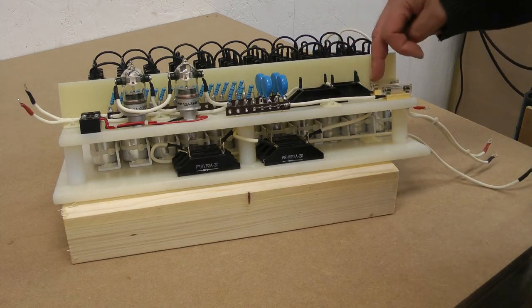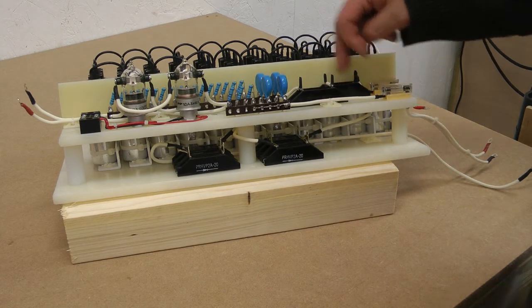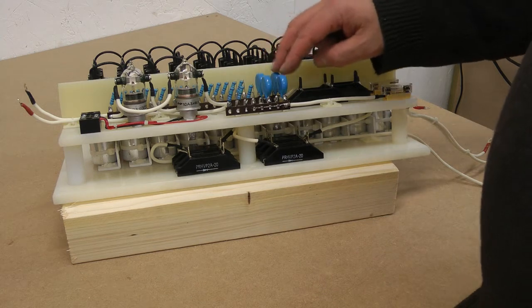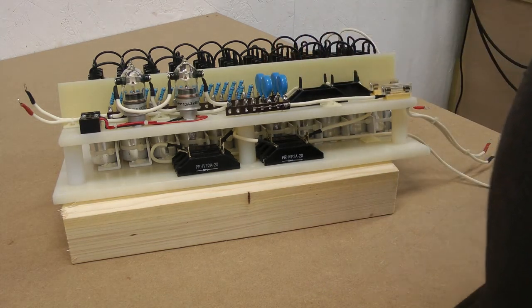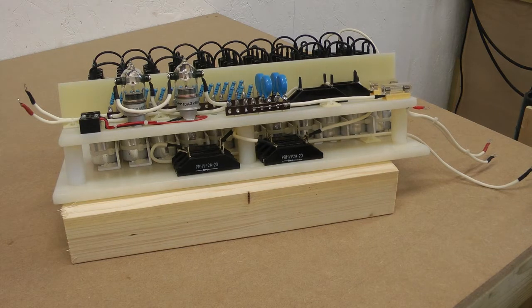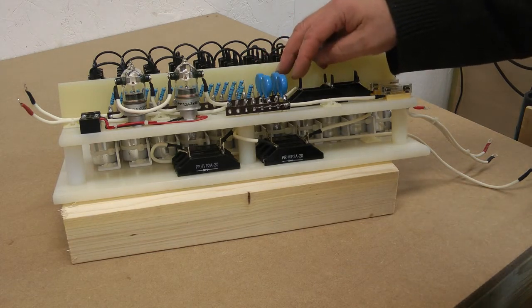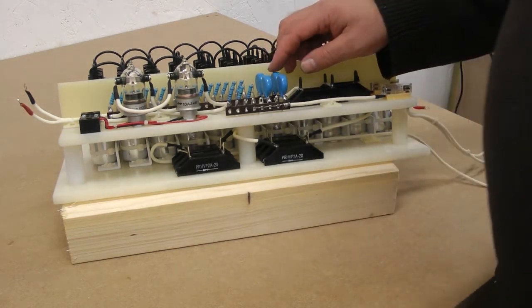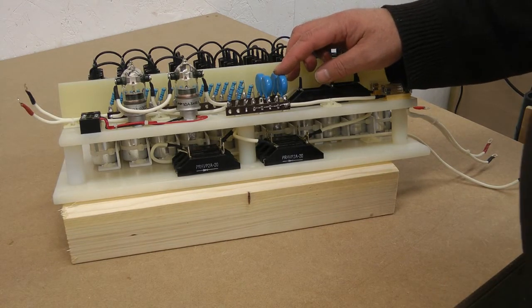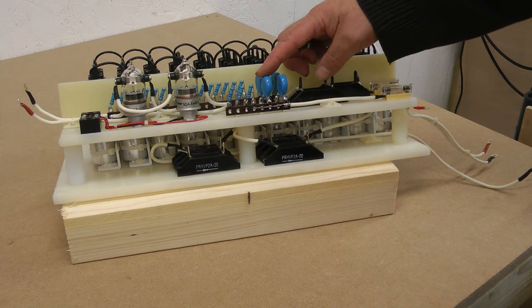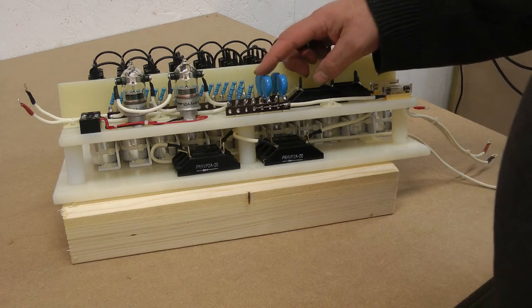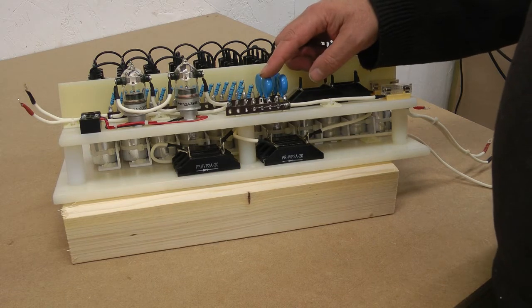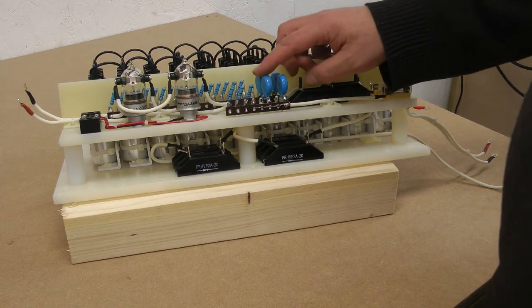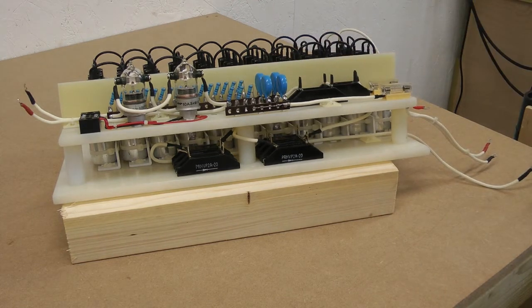So it comes through the half wave rectifier onto an accumulated capacitor bank here. That basically smooths out the ripple so that we can actually get a reasonable reading on the front if we were in raw mode. So those are 10 nanofarad each, 20 kilovolts, 10 nanofarad capacitors. So each two in series is 5 nanofarad, in parallel. So basically all four together produce a 10 nanofarad, 40 kilovolt tank capacitor for the measurement side.